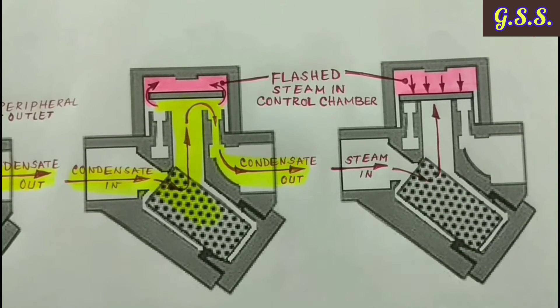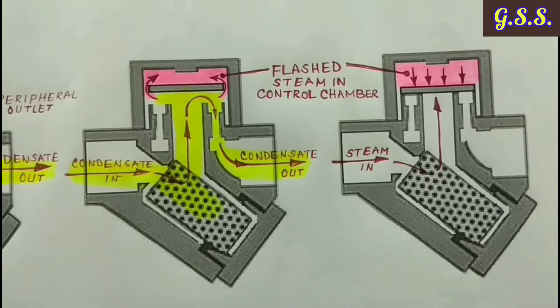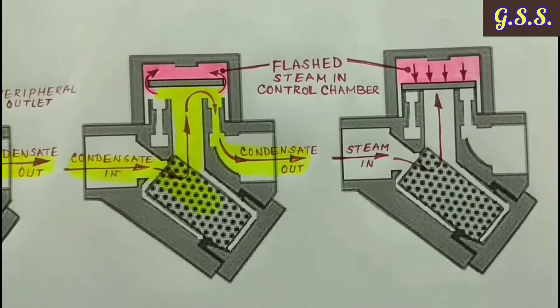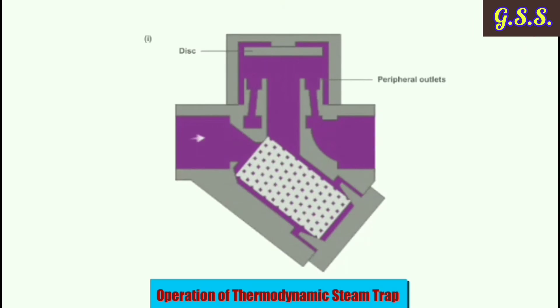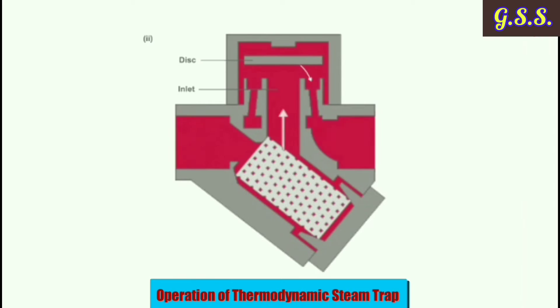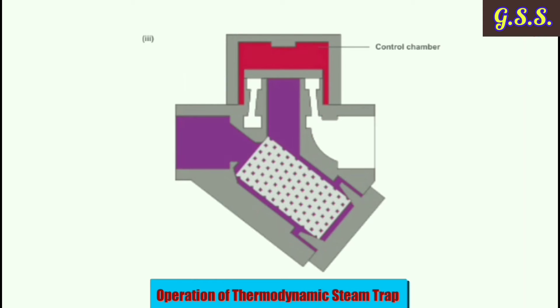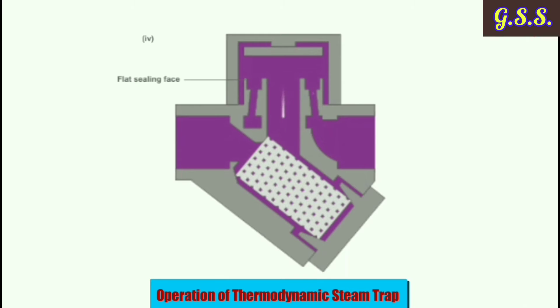Thermodynamic traps are most widely used due to their small size, wide pressure range, resistance to water hammer, and extremely robust construction with a simple mode of operation with only one moving disc. Now you can see how the thermodynamic trap works: condensate goes through it after pushing up the disc, and the flash steam is accumulated in the control chamber and closes the disc.